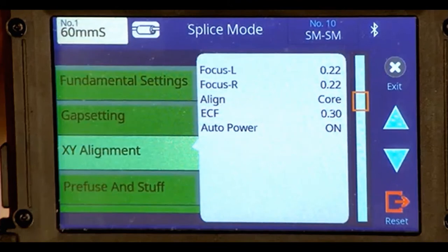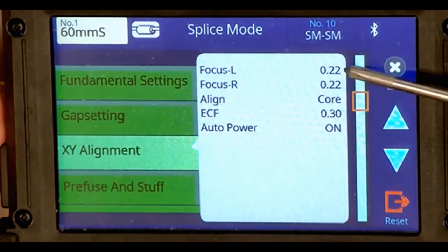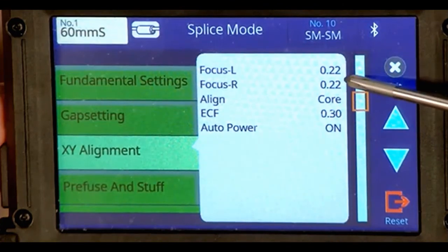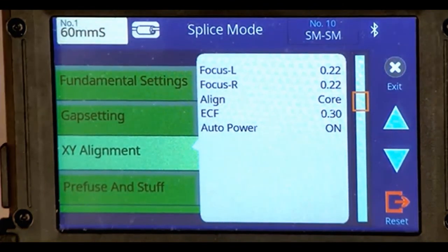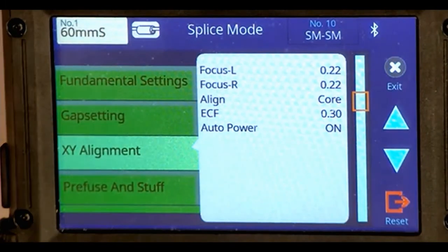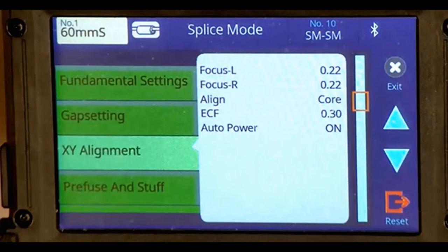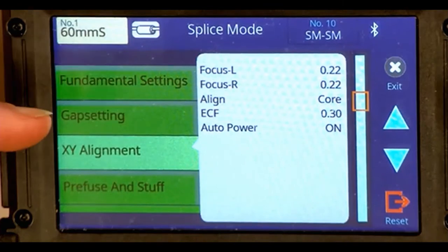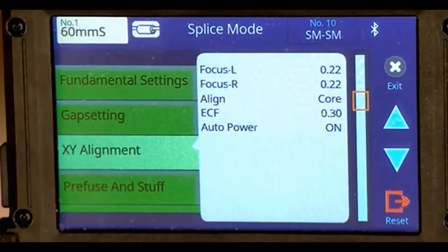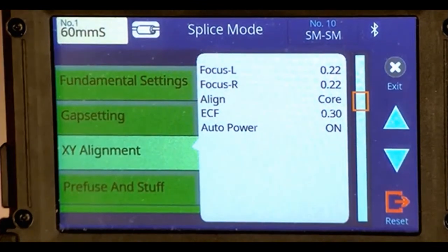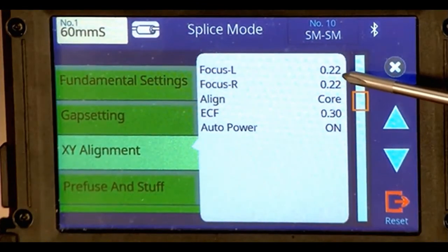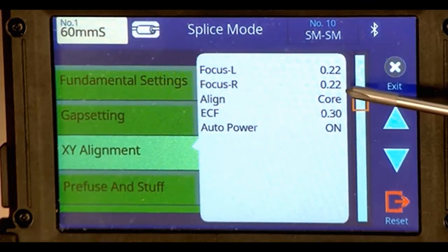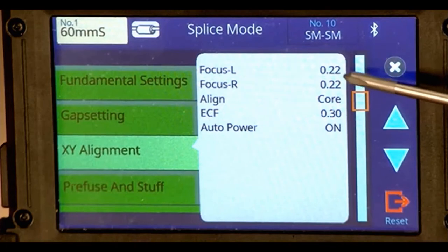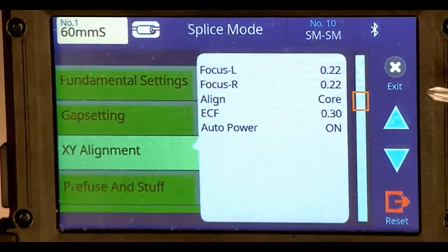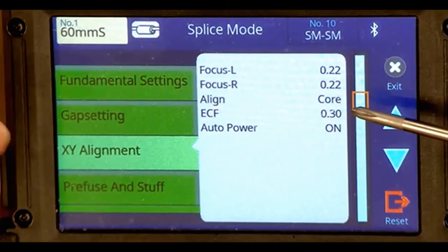For example, in the alignment, we can tell the camera what focus position we want to use. Normally in SM Auto, it's going to move the focus in and out a little bit to find a really good image, that really good sharp peak in the center of the bright area. But if we're only going to be splicing those exact same two single mode fibers, we may want to speed up the splicing time a little bit by setting it to a specific position. Or we may need a position that it wouldn't normally find when it does its search routine. Anyway, we're doing core alignment, not clad alignment.